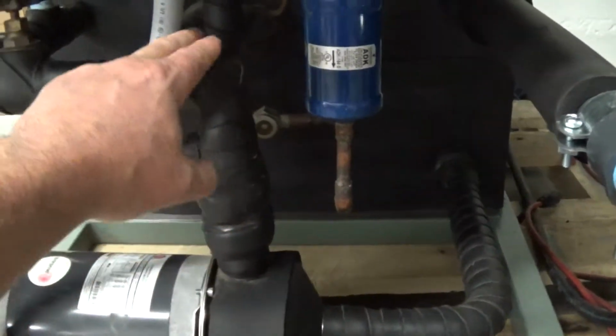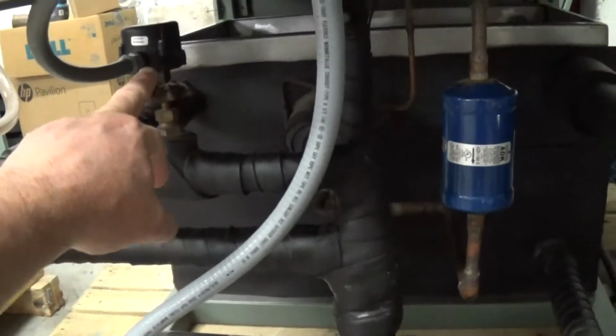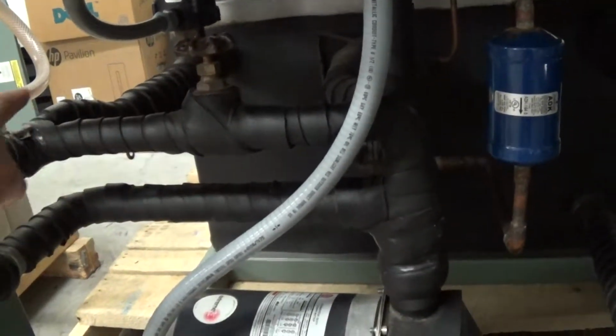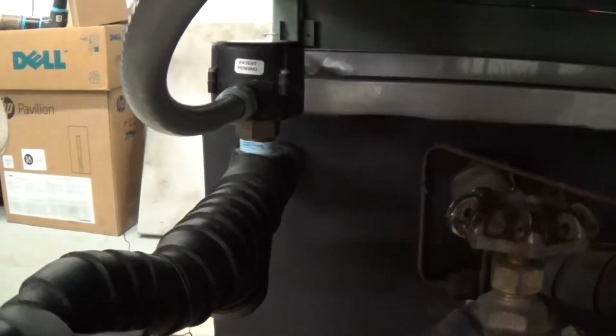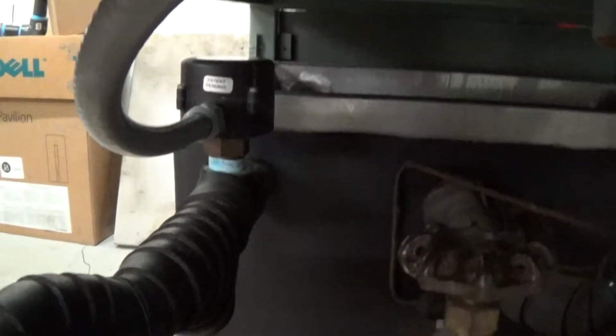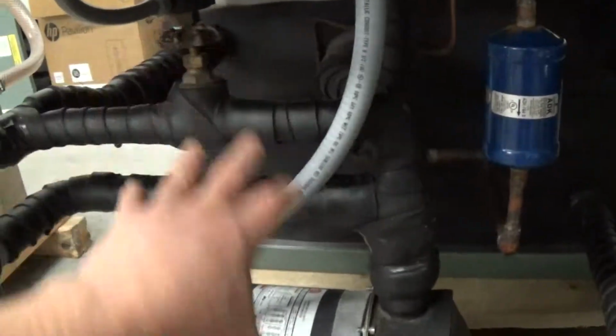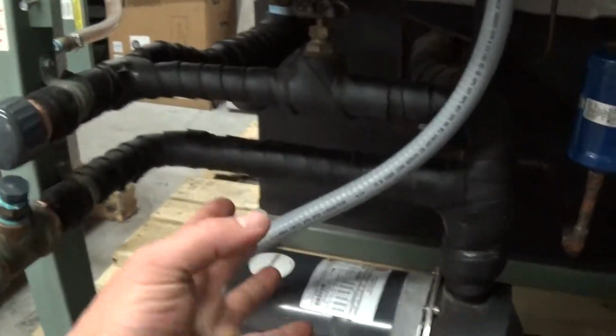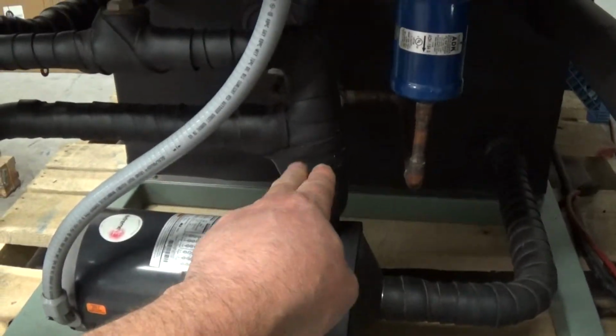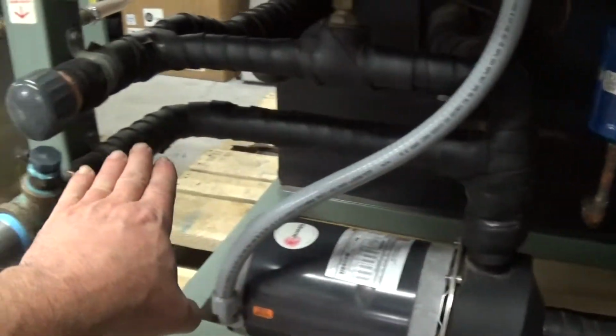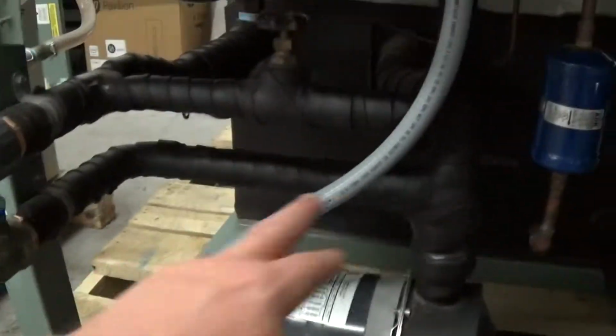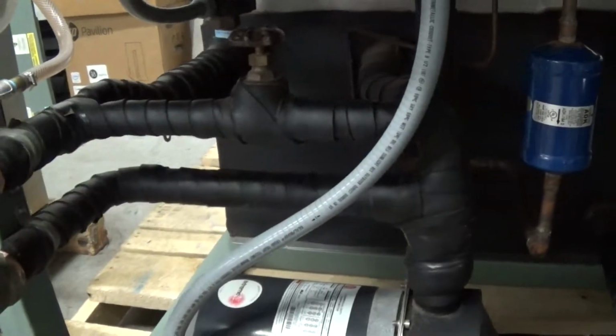We have a second line here with a globe valve that recycles back to the tank, and that goes into the inlet side of the brazed plate heat exchanger inside the tank there. What we have here is a flow switch to sense flow. With this valve here, you're going to balance the output of the pump. Essentially, it's almost teeing off here. Part of your flow is going out to your process. The other part of the flow is going directly back into the heat exchanger.